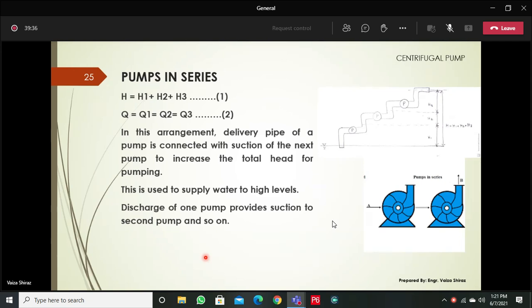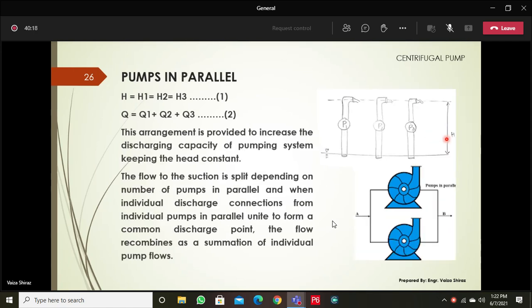If you have more than one pump, connecting them in series means the delivery pipe of the first pump becomes the suction pipe of the second, and so on. This raises the head, but the final discharge remains unchanged. When pumps are connected in parallel, the pressure head remains the same but the discharge is increased. So where you need to increase discharge, install pumps in parallel; where the purpose is to increase head, install pumps in series.